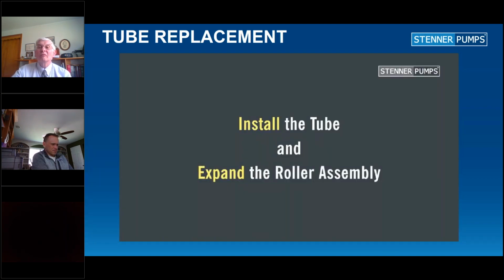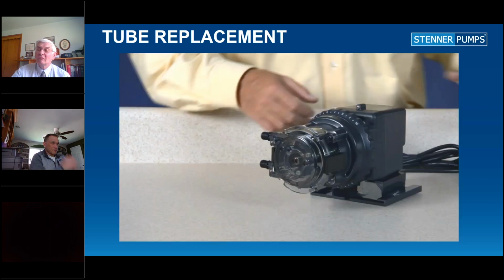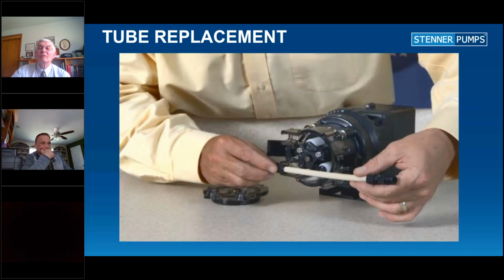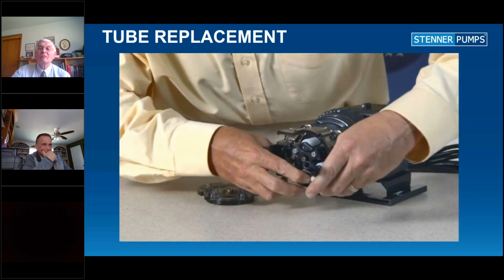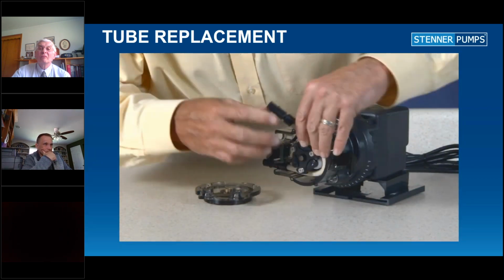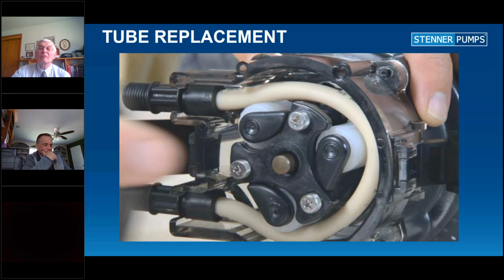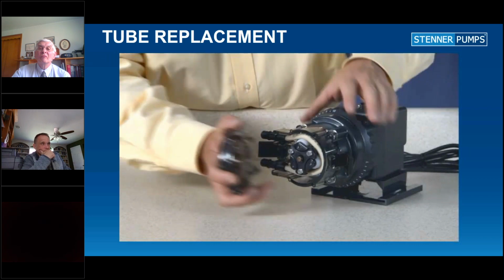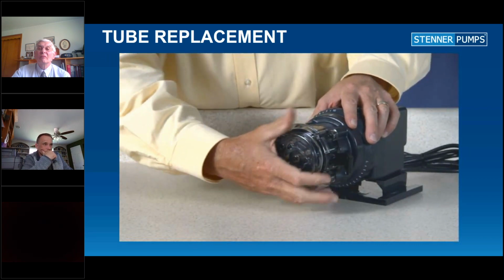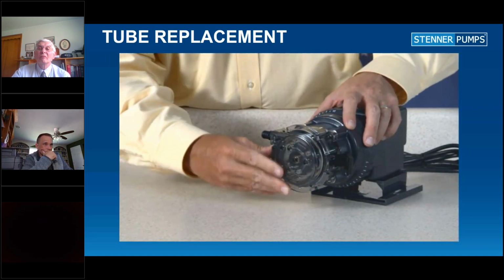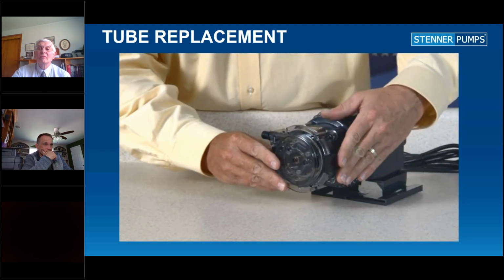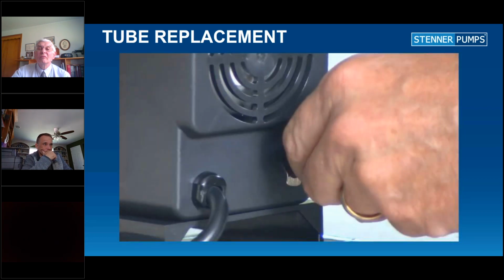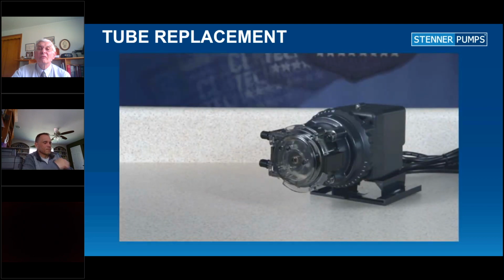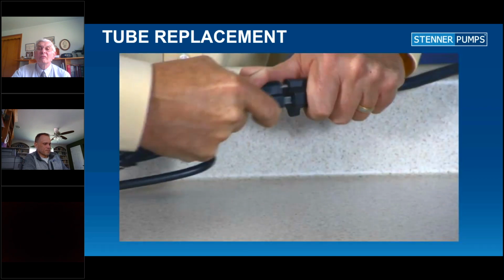Now we will install the tube and expand the roller assembly. Check the feed rate ring and make sure it's set to 10. After removing the tube housing cover, place the new tube in the pump head. Use your fingers to center the tube over the rollers. Note that we aren't going to expand the roller assembly at this time. We'll do that later. Place the tube housing cover feet first on the tube housing. Attach the front of the latches to the cover lip, then snap the latches back to secure them. Now that the cover is latched, plug the pump in and turn it on. Allow the pump to run with the roller assembly in its collapsed position about 2 minutes to relax the tube. Then turn the pump off and unplug the power cord.